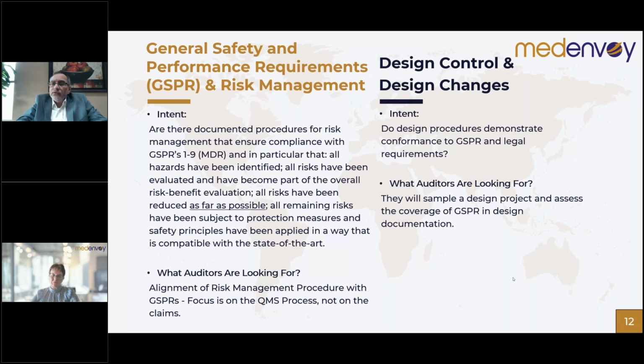Then general design and design control and design changes management. Primarily, we will be relying on ISO 13485 as an auditor. So your process for design and design control must be compliant as per 13485. But as I mentioned, what we are looking for under MDR is that you are identifying GSPR and all the other MDR requirements as your design input. So within your design documentation and design procedures, it should be visible that MDR considerations have been taken into account. It's not an afterthought. You don't prepare your technical documentation once the product is ready. You follow the process from the beginning, and you are aware of the requirements at design input steps. That's the fundamental point, and this is what auditors look for, that when we look at sample documents, sample projects, we look at how you identified MDR requirements in your project design specification and inputs.